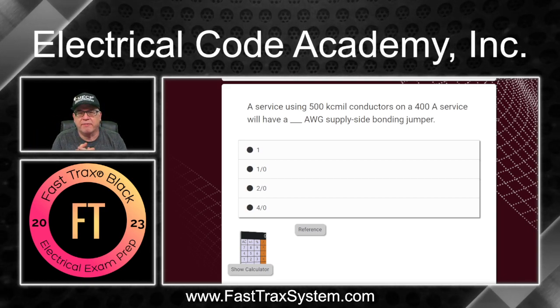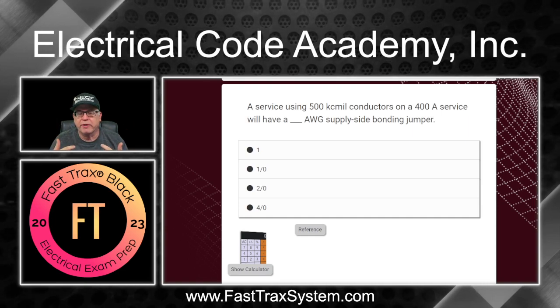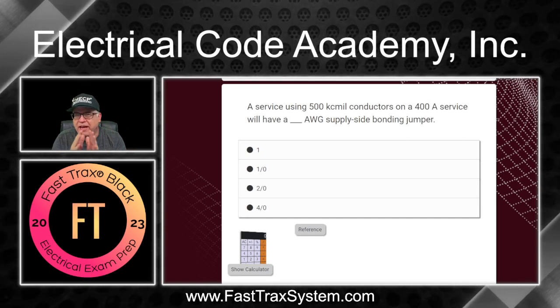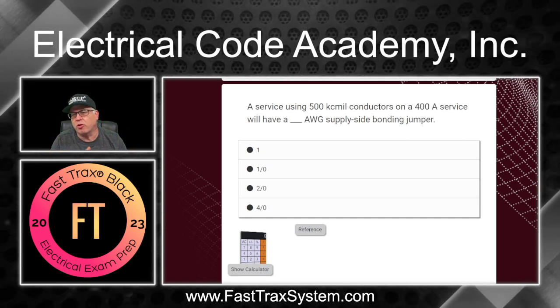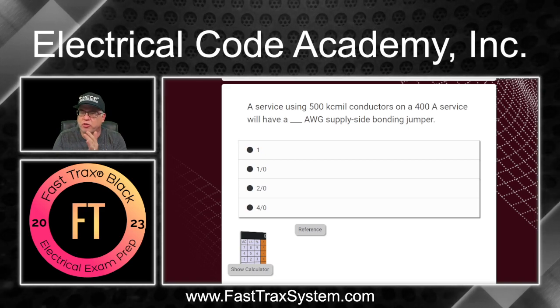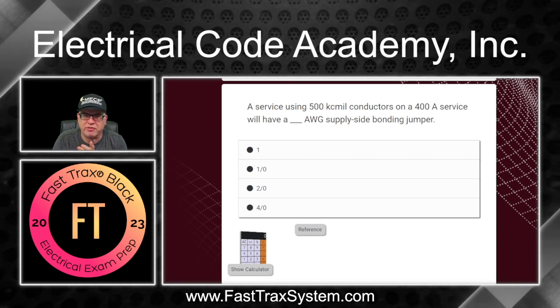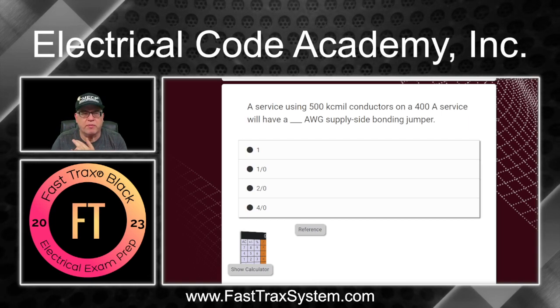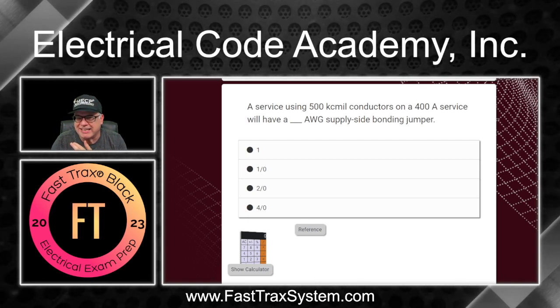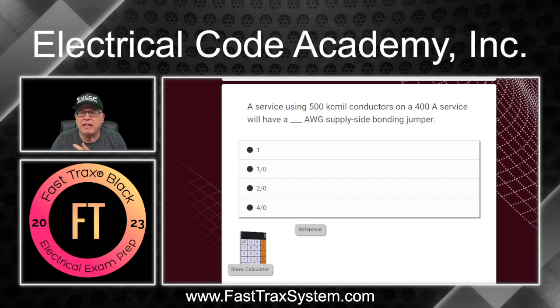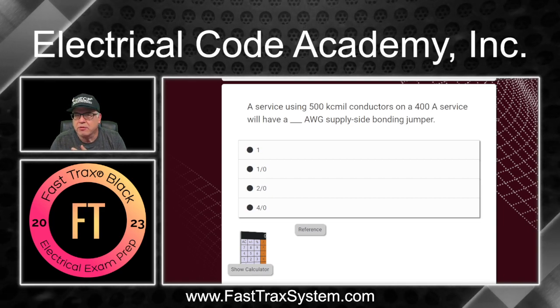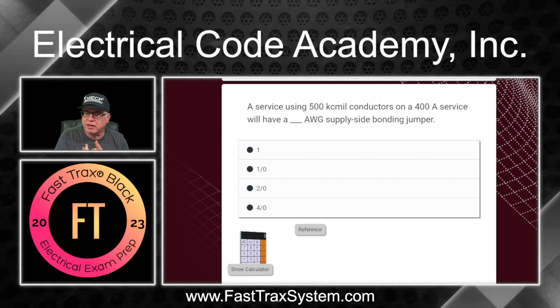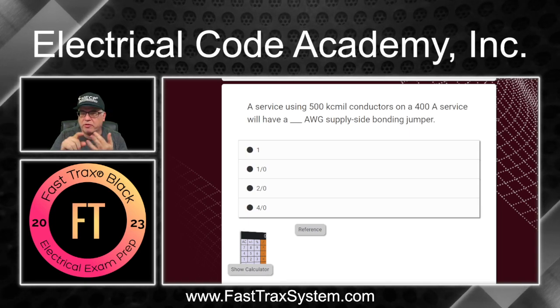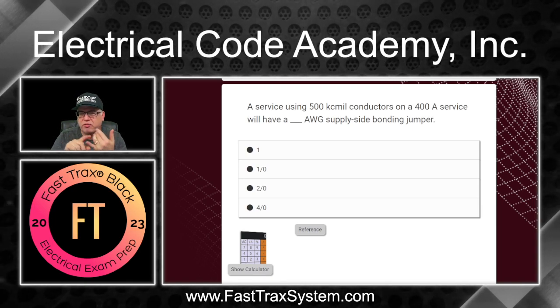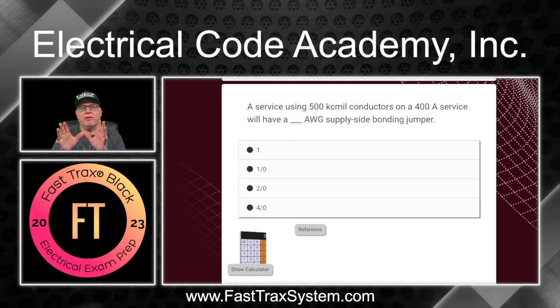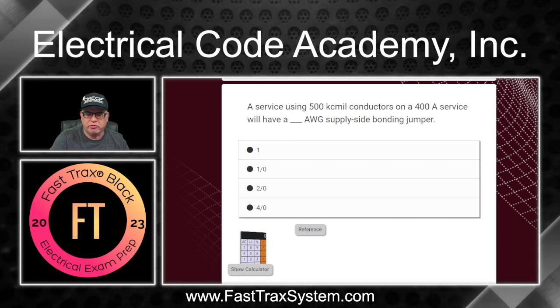This is why I tell you folks, it's so important to learn tables and certain things in the code and do your best to commit to memory. Remember, 250.66, grounding electrode conductor sizing, okay? 250.122, equipment grounding conductor sizing. 250.102(C), sizing: minimum size for the grounded conductor, supply side bonding jumpers, main bonding jumpers, system bonding jumpers, all covered by that table. That's where we're going to go. So let's go to the code.